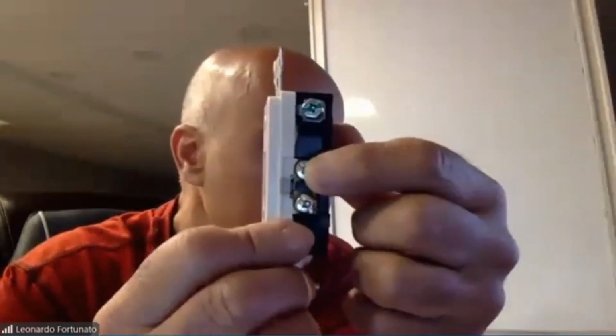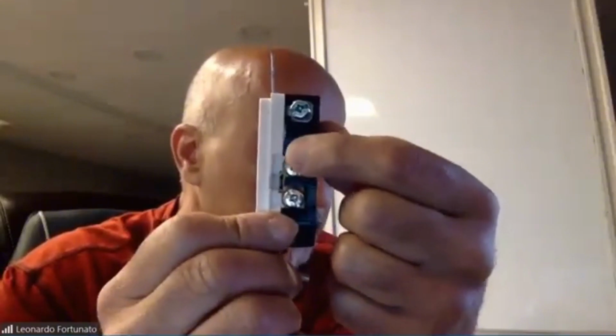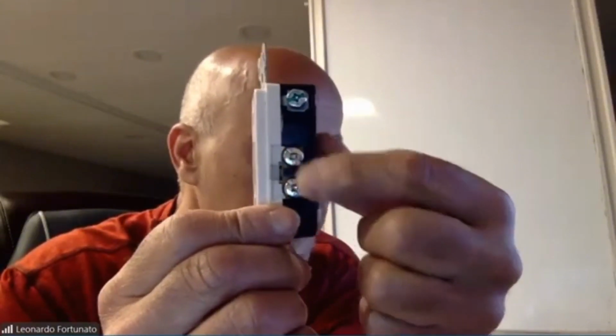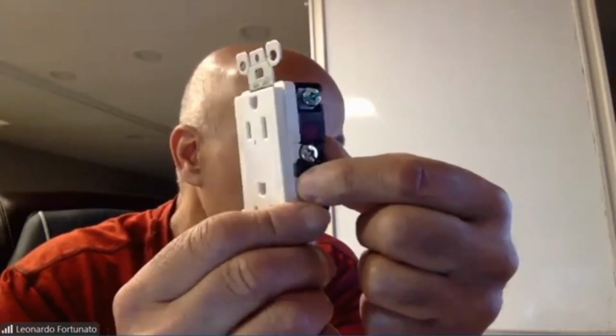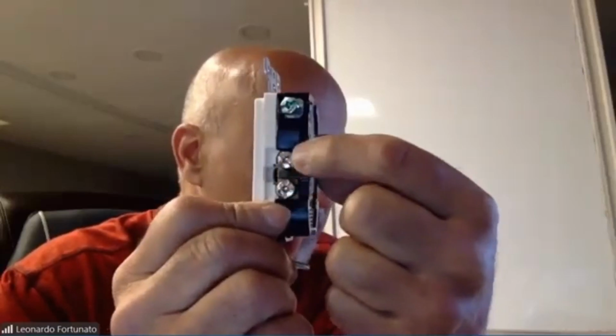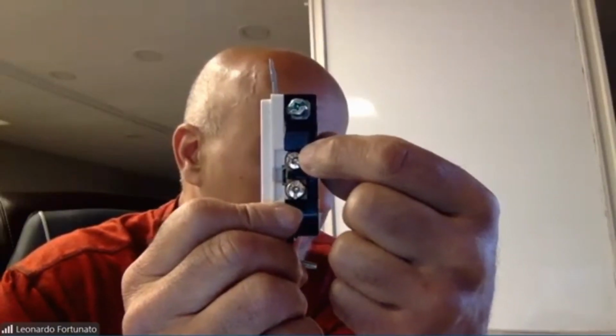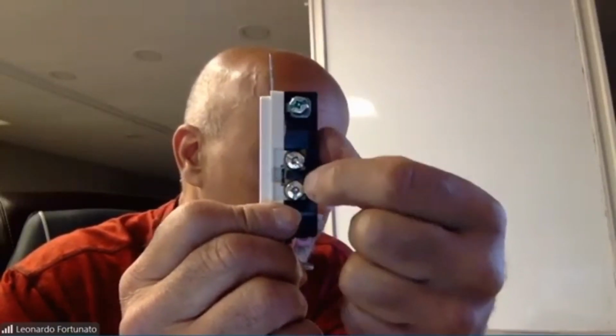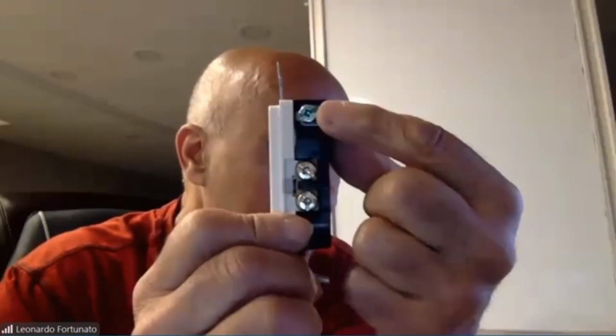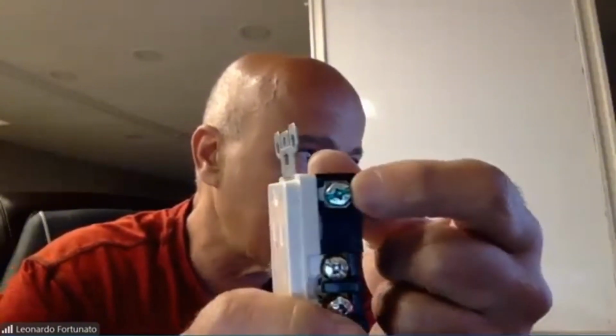Also in behind, we've got 2 screws here, and on the neutral side, I can connect my neutral here or here. It doesn't matter, because if I connect it here, this tab is going to make the neutral go there as well, so they're interconnected. Again, there's a ground screw, indicated with a green screw.